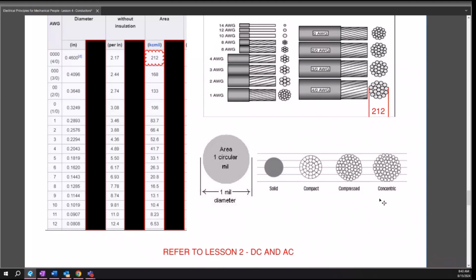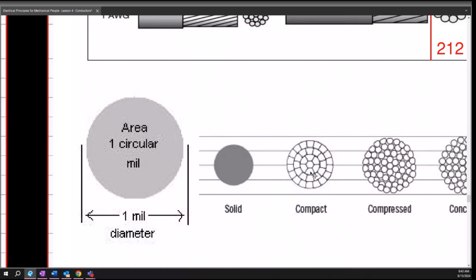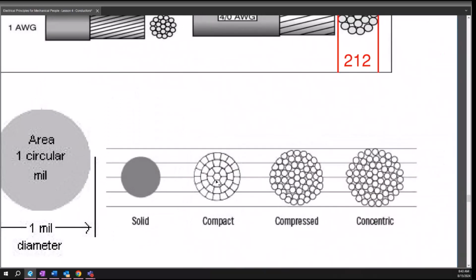The only other thing I can think of is, when you have concentric, it's going to be a little bit more flexible, whereas the compact is not—these individual copper strands are going to have a harder time sliding against each other because there's no air between them. But that's on the install side, so as long as you're not doing something stupid on the installation, like putting it on a very tight bend radius, don't worry about it.